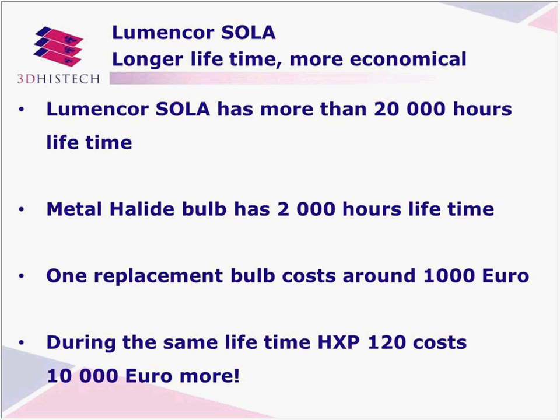And it's not just the money, but also the downtime. The customer has to order the bulb 10 times, go in, and change the bulb, and there is downtime. With the metal halide, it's not that for 2,000 hours you get the best quality and after that it quickly dies. The lamp decreases continuously during the 2,000 hours. The first 500 hours are quite okay, but the last 500 hours are quite bad compared to the first 500 hours. With the Lumencor SOLA, you don't have to worry about the light for many years, and it has better quality during that time.